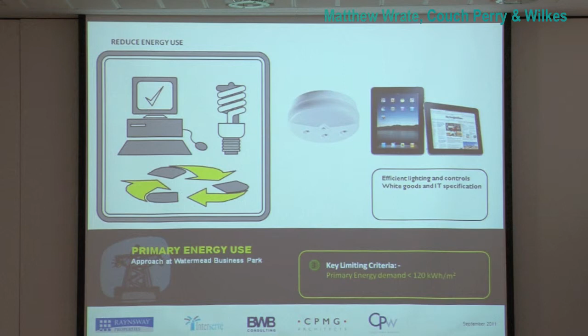This was on the morning of the air tightness test, where we'd calculated the 0.6 requirement as passive house. That translated on this building into Part L terms as an air tightness rate of 1.19 metres cubed per metre squared per hour at 50 pascals, the units we're more familiar with. So that was their limit, 1.19.